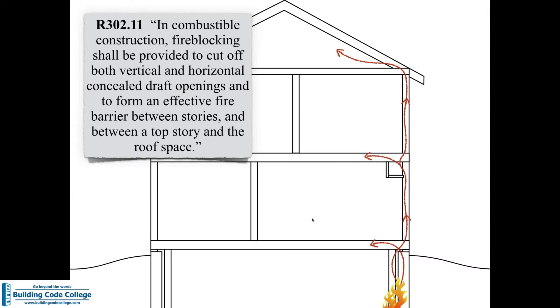R302.11 will tell us what fire blocking is — in combustible construction. Fire blocking shall be provided to cut off both vertical and horizontal concealed draft openings and to form an effective fire barrier between stories and between a top story and the roof space. What fire blocking does is put stopping points to stop hot gas from running through and compartmentalize that concealed fire. Hopefully a concealed fire in the basement will be compartmentalized and will breach the wall covering and set off the smoke alarms before it has traveled all the way up to the attic. That's about buying time for escape.